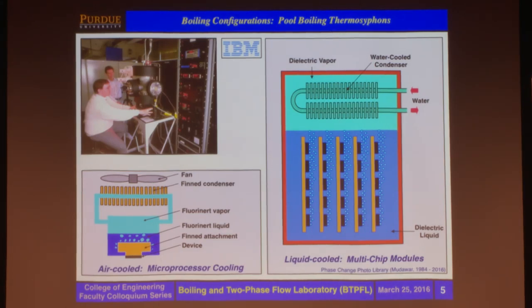The simplest configuration is the thermosiphon that you see right here, where at that time the thought was to submerge all the electronics of a mainframe in a pool of dielectric liquid. Heat is dissipated by forming bubbles, which rise by buoyancy. They're recondensed by a water-cooled condenser. Within the system itself, there is no pump—it's passively driven, and that's a major advantage, obviously, from a cost and reliability standpoint.